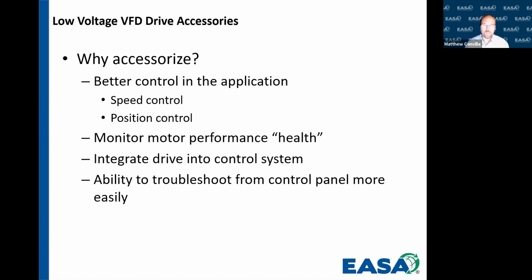So in some instances, we want better control of the application. We need more precise control of speed and position. So we have accessories for that. We may want to monitor the motor's health or the performance of the machine. So we have some accessories that we can use for that. We could want to integrate the drive into the control system. Maybe we don't want it to be standalone. We want to be able to control it remotely, or we want to know what its functionality is, what it's doing at an exact moment in time. So there are different accessories for that. And lastly, we might actually want to be able to troubleshoot from the control panel or the drive panel more easily. And there are different things that we can do to accomplish that as well.